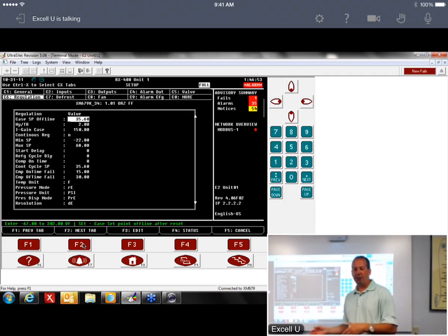Well, after the installing contractor left the job and it was left in the hands of the servicing contractor, they started having a lot of problems. They called us down to take a look. Steve Yates and I went down, and we found every case in the store had the parameters dumped into the E2, and we had to delete every XM device in the entire store and re-add them. Between the two of us it took about 2.5 hours, and that was probably 70 cases in the store. So it's not a massive undertaking if you have to do that, but that's the best way to do it. Delete the device and re-add it.